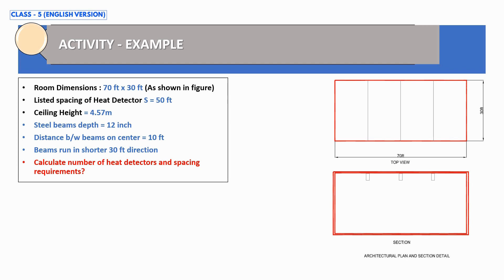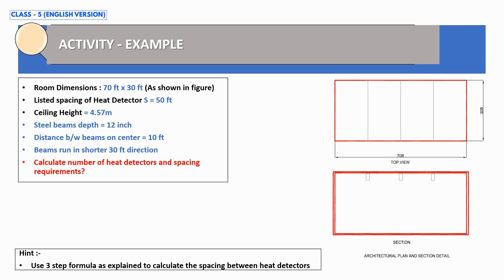As a hint: use the three-step formula already explained to calculate the spacing between heat detectors. Note there is a table to calculate design spacing when ceiling height is more than 3 meters. Since this building has beams, apply the additional reduction factor for beams and then calculate the number of heat detectors and spacing requirements. Put your solution in the comment section and I will confirm whether your answer is correct.